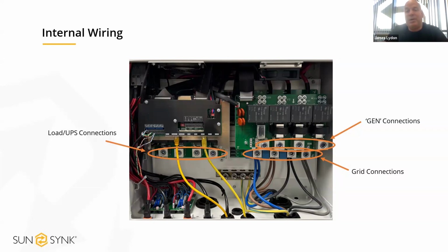But what you can do if someone is completely off grid and they need a backup generator connection, but they also want to have the diverter connected, we can move the generator grid side. So you can connect your Jenny to the grid terminals, and that then frees up the generator port to allow us to use that as the diverter. The only thing the installer would need to do if using the grid connection for the generator supply is there's a tick box on the inverter to say that the Jenny is connected to the grid. Those grid terminals are typically looking for between 47.5 and 51.5 hertz. The Jenny's going to go way outside that. So when you tick that the generator is connected to the grid, the inverter is just going to widen those tolerances to let the system synchronize with it.